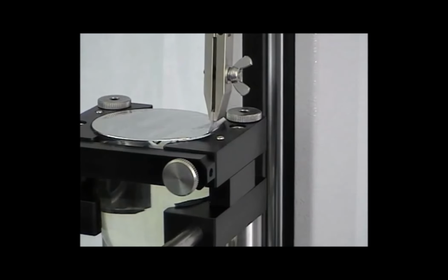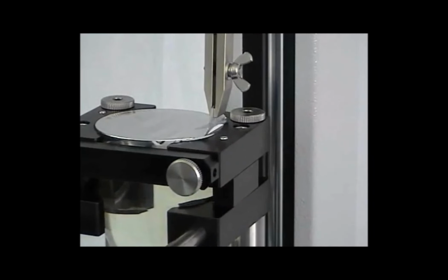So as I mentioned, the applications for pressure-sensitive tapes are endless. Food, cosmetic, medical, packaging applications, just to name a few. This next video is of a peel test on a foil sealed wine glass and is conducted using a software driven force tester. The peak and average forces needed to remove the foil lid from the wine glass are measured, and the results are displayed graphically using the force measurement software on the tester.